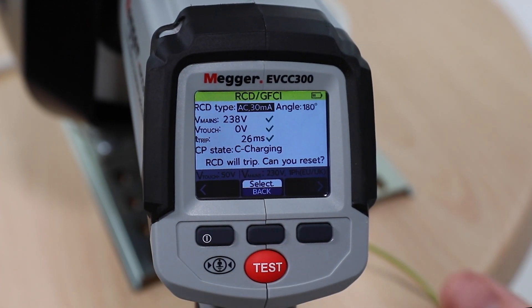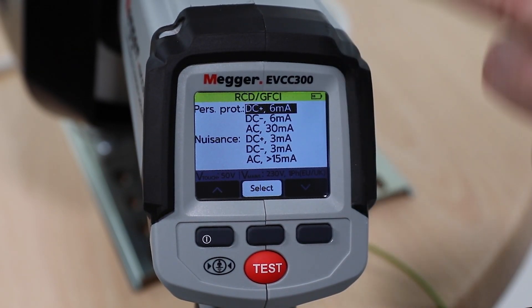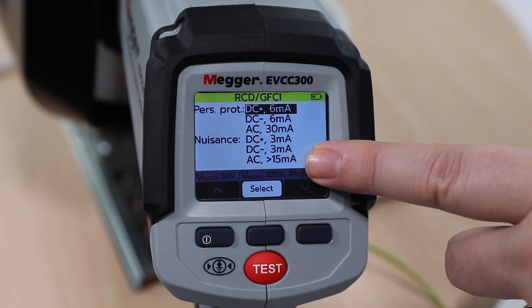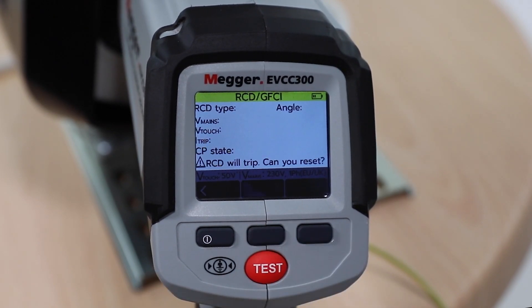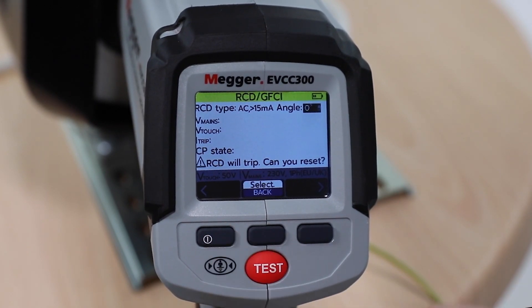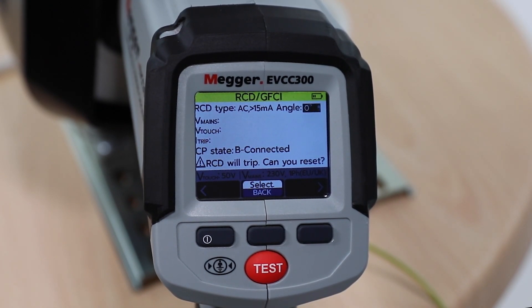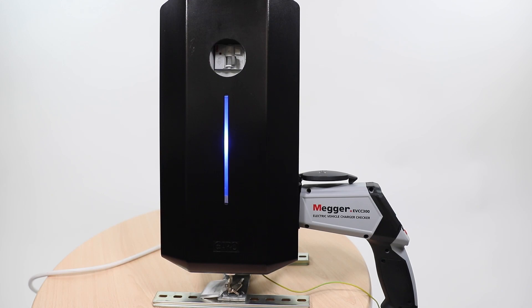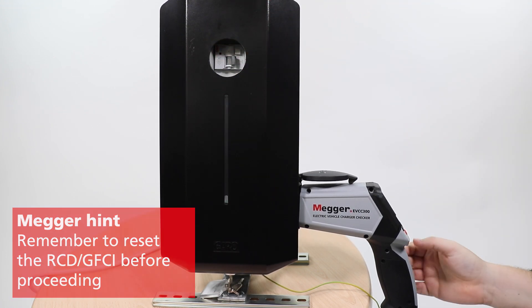In the RCD type section, scroll to the nuisance options and select the rating that is higher. For example, for a 30mA RCD, select the >15mA AC for nuisance. Select the angle to be tested at either 0 or 180 degrees. Press the test button for 2 seconds and release. Note the test results — is the trip time sufficient to avoid unwanted tripping of the protective device? Don't forget to reset the RCD/GFCI before continuing.